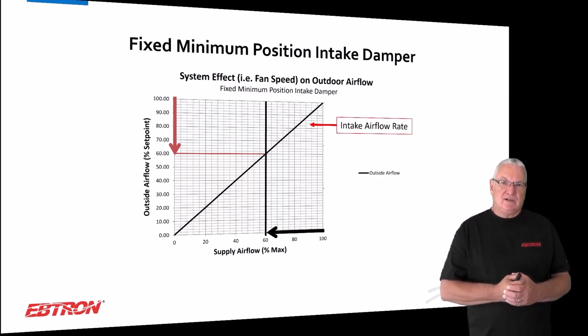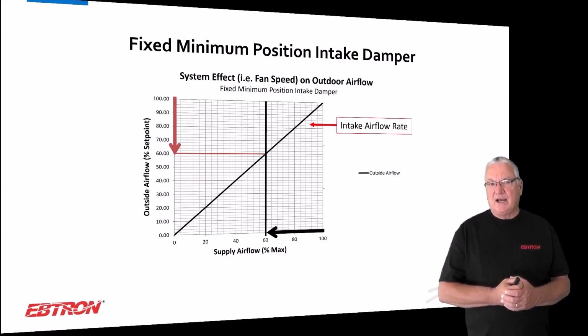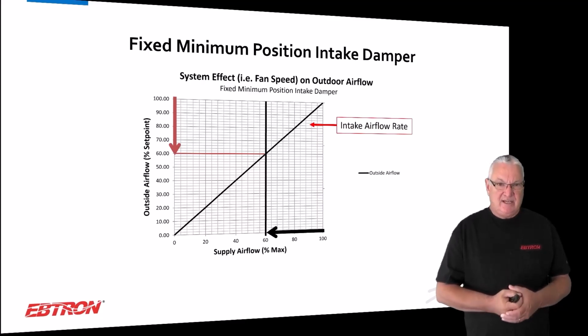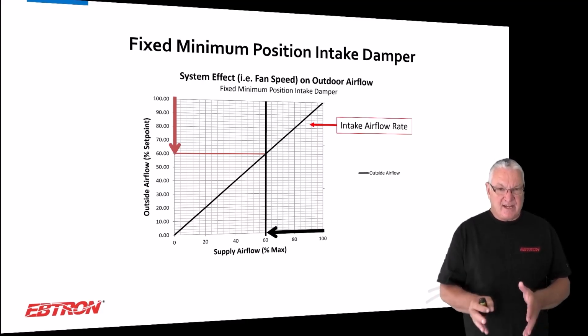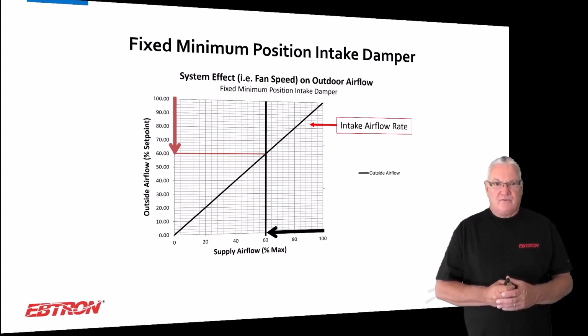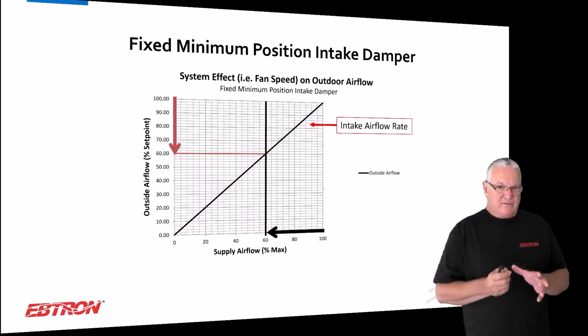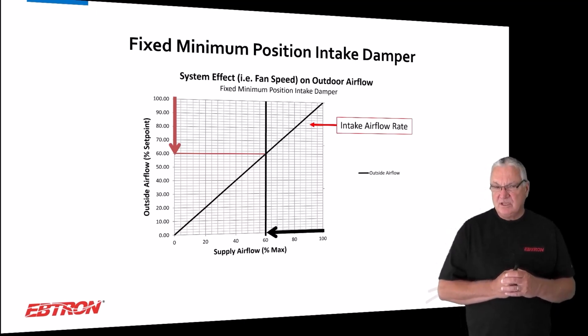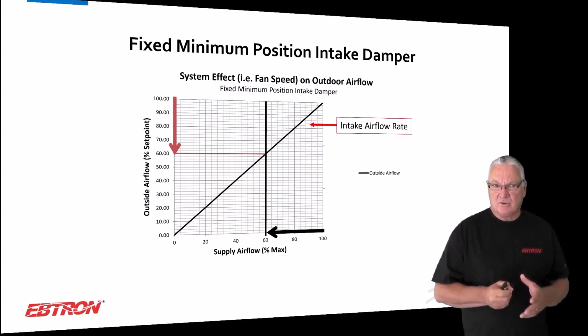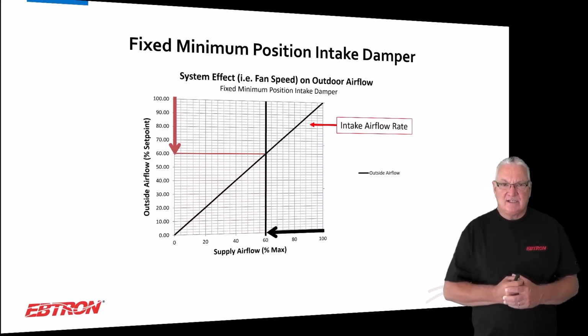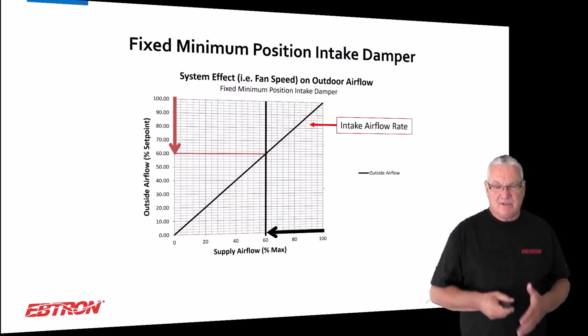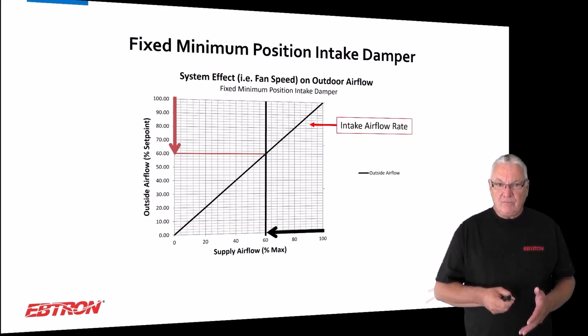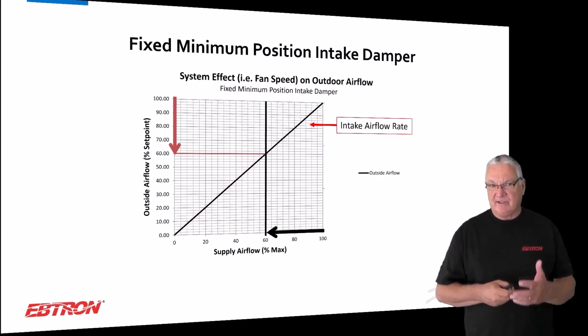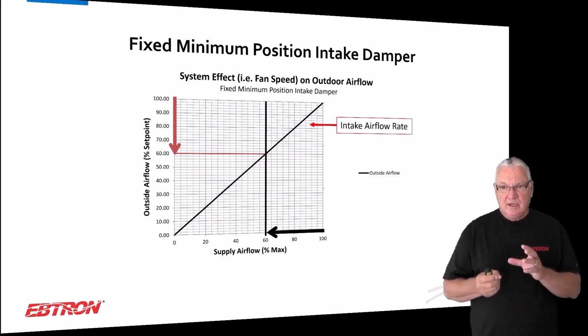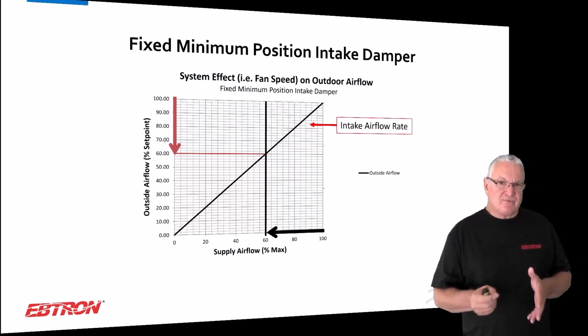Now, I think that that's pretty well understood by most people. I don't think they always look at that it's not just VAV, that it's constant volume with multiple variable speed, or at least even just 2-speed fans. It's also fan coils. In a little different way, it's DOAS to multi-zone systems that have some kind of demand control ventilation. So, I'm looking at it as a VAV system, but don't think it's only VAV that has this problem, and don't think it's only a system with a supply fan. Supply return fans, supply relief fans, they have the same types of problems. It's just harder to make a general discussion about it.